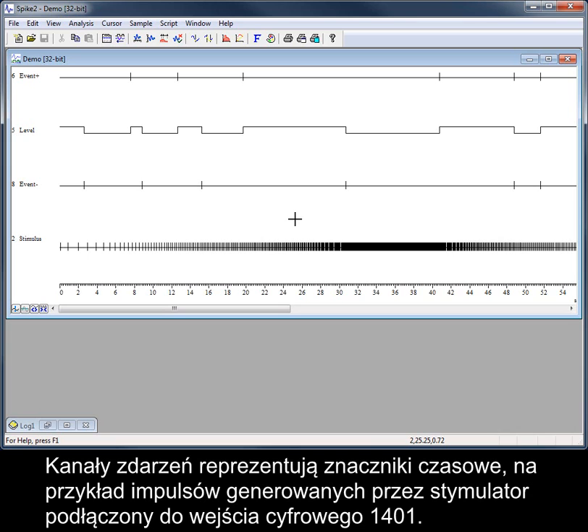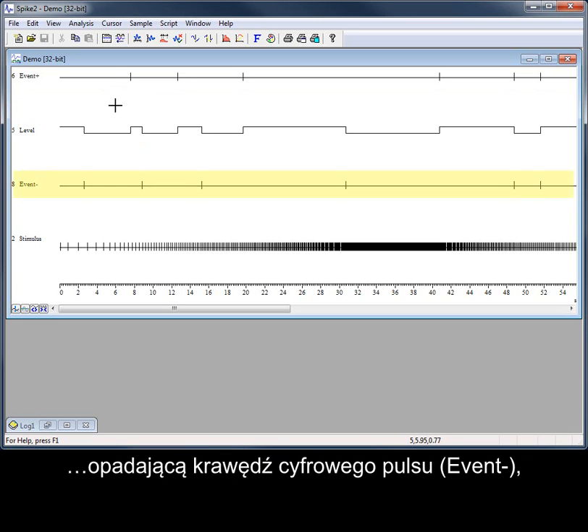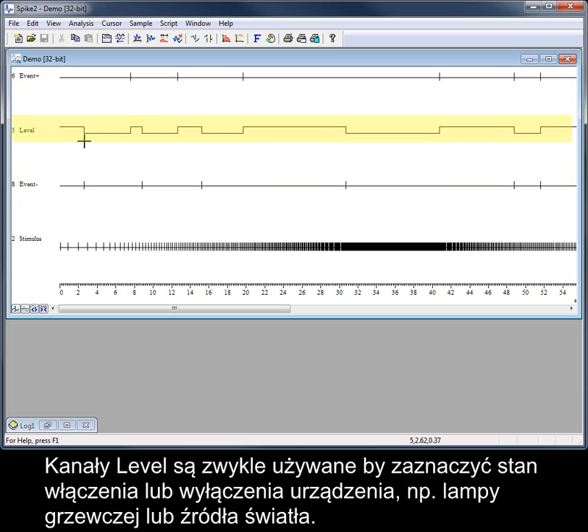Event channels represent timestamps, such as the pulse output of a stimulator connected to a 1401 digital input. Spike 2 records these timestamps based on the rising edge of a digital pulse, the falling edge of a digital pulse, or both edges as a level channel. Level channels are usually used to indicate the on or off state of a connected device, such as a heat lamp or a light source.